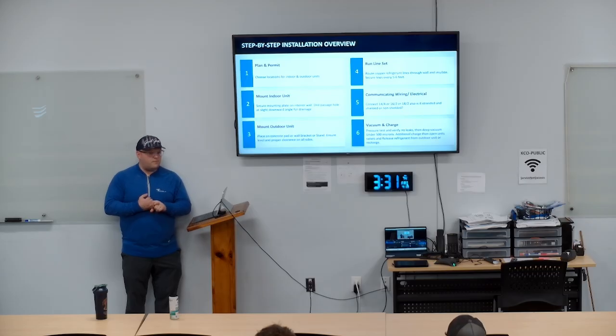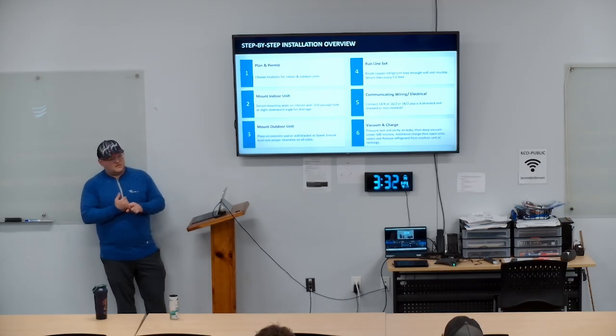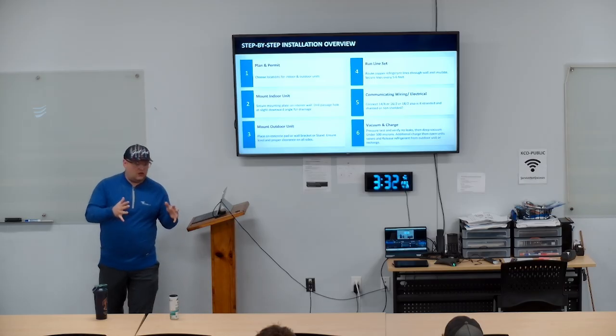We will help. But again, if it's ducted, sheet metal guys should be doing it because their ductwork is going to be a lot harder to manipulate than our line sets that we can bend over and come back in. And normally they're bigger. So if you have a ducted unit and it's a 36-inch by 8-inch opening and they've got to blow it up to a 24 by 18 or whatever they're going to do, they need a lot more room than we get. So if it's something that's ducted, we prefer that they set the unit.